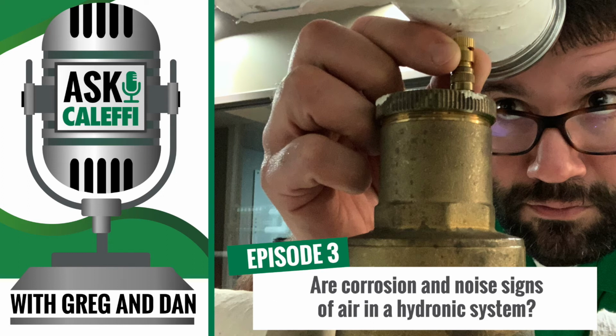We get that question a lot about an air separator for plumbing, and they're great for air removal. They're more for a closed system, so you're not going to put that into a plumbing application. Right. They're not low lead brass. They're not designed to be in what's called an open system. Right. So putting those in, Greg, I often see the fill and expansion tank hung below them.